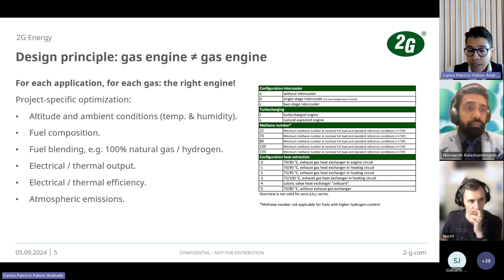We also optimize the engine for the specific site where it's going to operate. Beyond our standard versions rated at ISO conditions - 25 degrees centigrade and sea level altitude - we also have high altitude versions, with which the engine delivers the same power output at 2,000 meter altitude as at sea level, or the same power output at 40 degrees centigrade as at 25. So we have special versions in terms of altitude, temperature, and also site requirements like NOx and CO emissions. We're able to optimize the engine for each project, including the fuel gas.